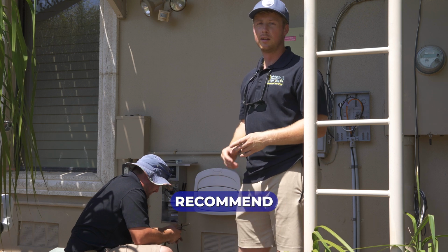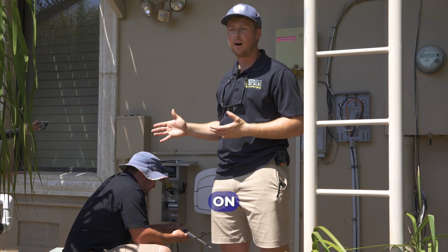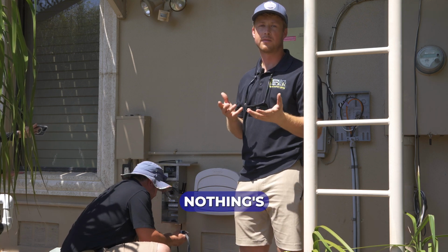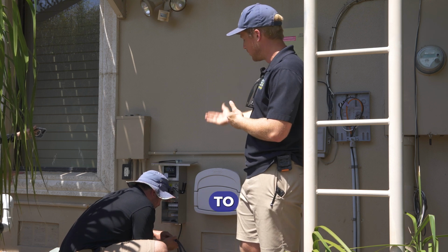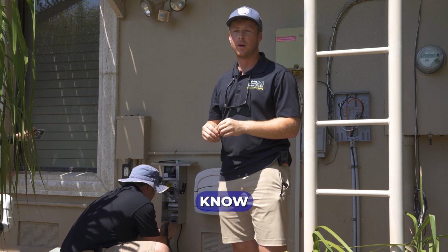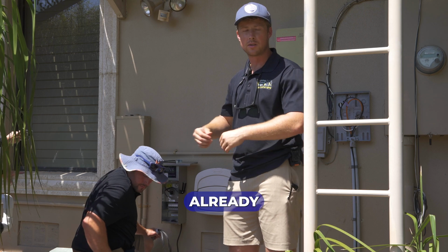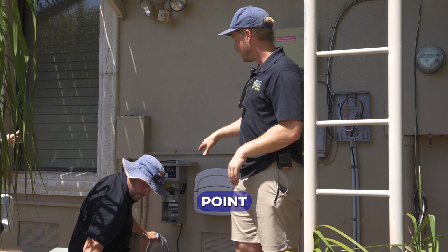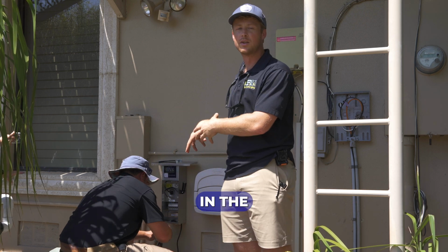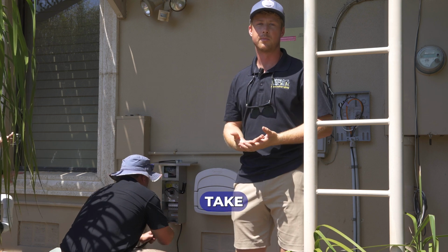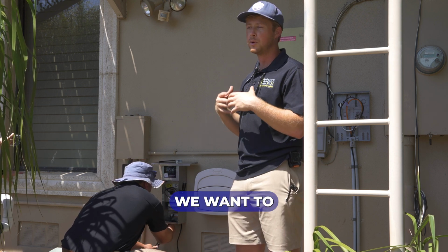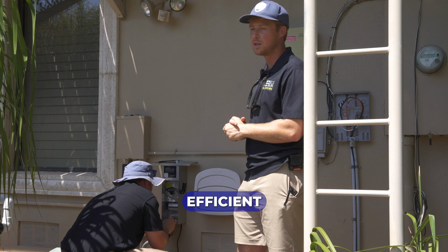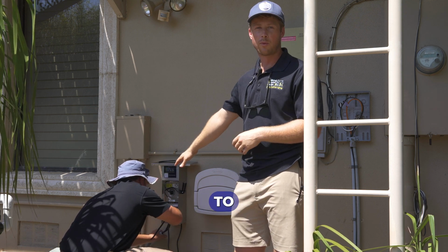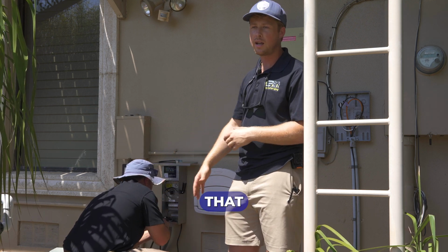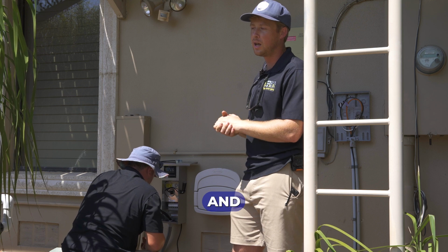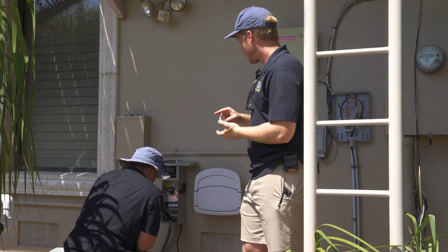I always recommend leaving some extra slack on the wire to work with, because nothing's more annoying than having to extend your wire run. Essentially if you don't have enough wire already trenched at this point and you need more wire to do a connection in the transformer, it's just an extra step. It's going to take more time, and we want to conserve time and be efficient here. So we've got plenty of extra wire to work with. We won't end up using all of that. We'll strip back what we need, and we'll connect to the transformer.